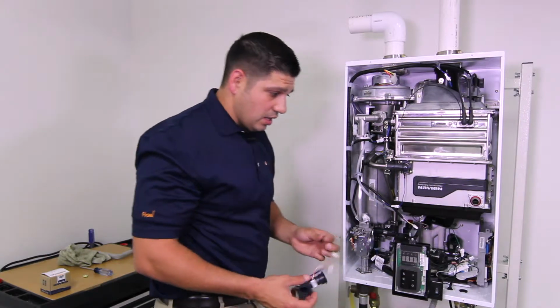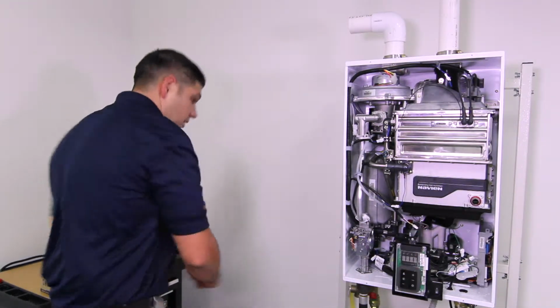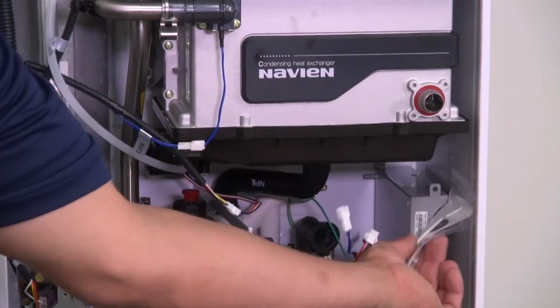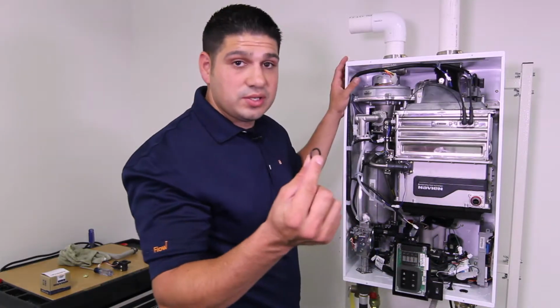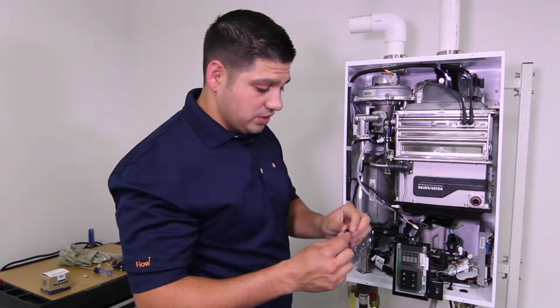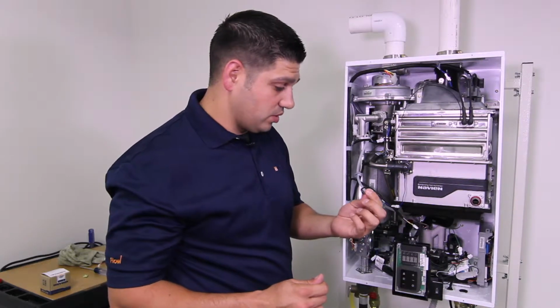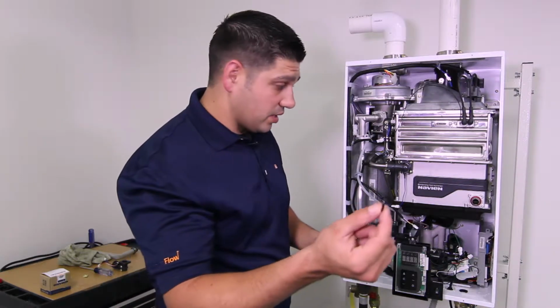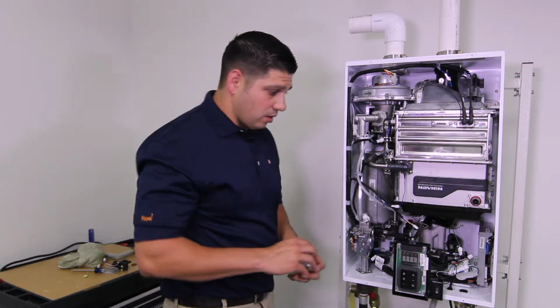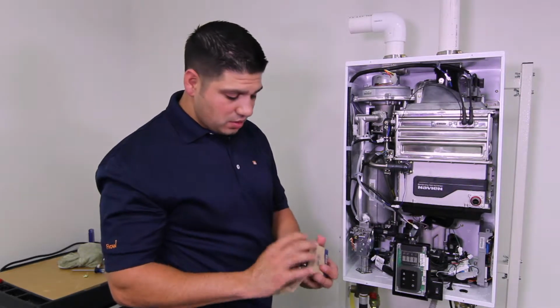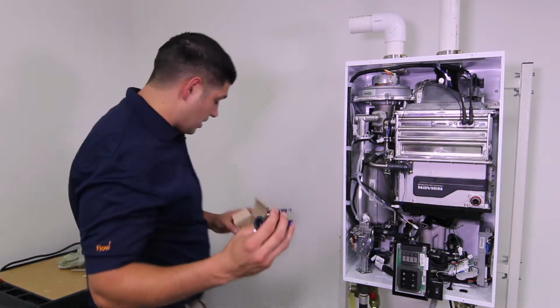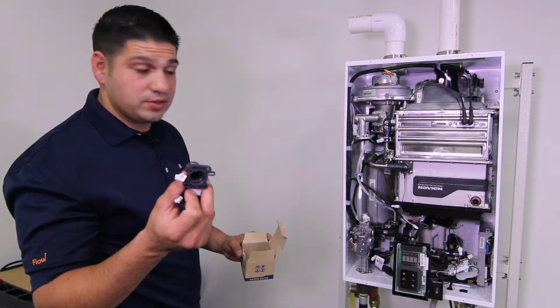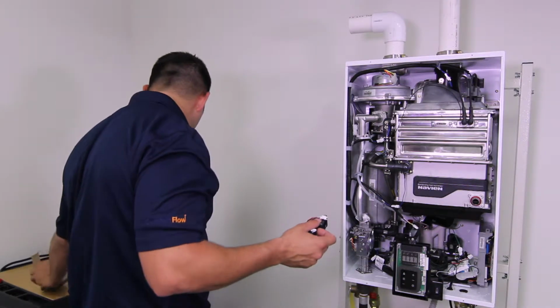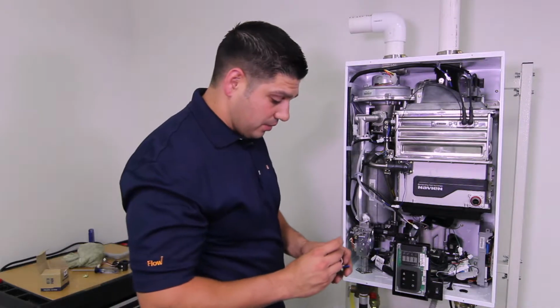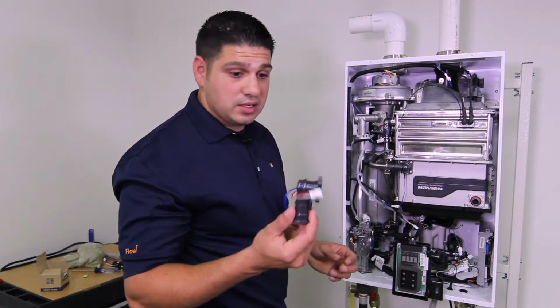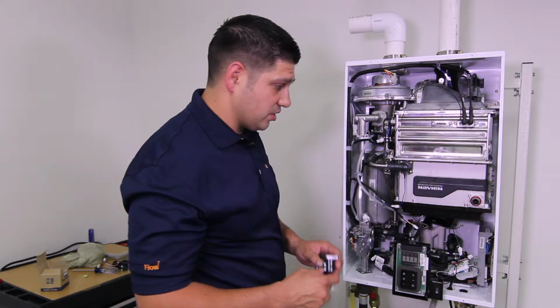Make sure your unit does come provided with some replacement O-rings in this kit over here, but if your O-ring is still good, you can reuse it. Just always inspect it anytime you're reusing a part. Inspect it for any leaks, cracks, tears, or pinches. We're going to pull out our replacement flow sensor. Also do a thorough inspection on your replacement parts. You're only provided your flow sensor, so you may have to use some of your old hardware and your old O-rings. Just do a thorough inspection that there's no shipping damage, no cracks, tears, or pinches.